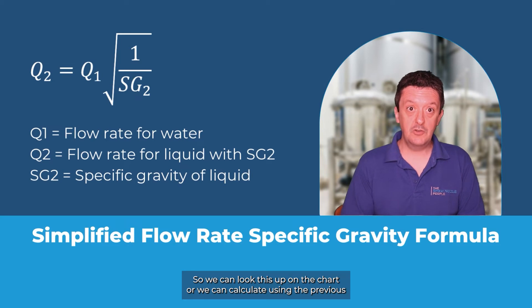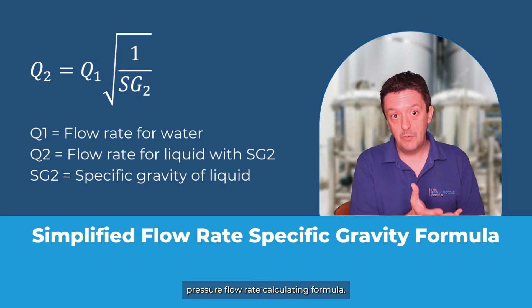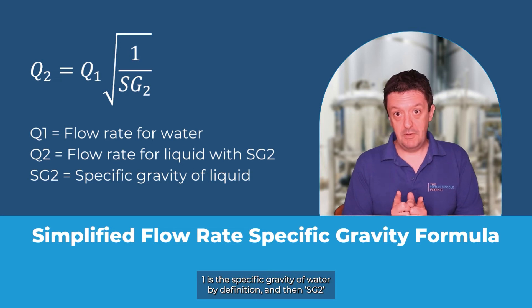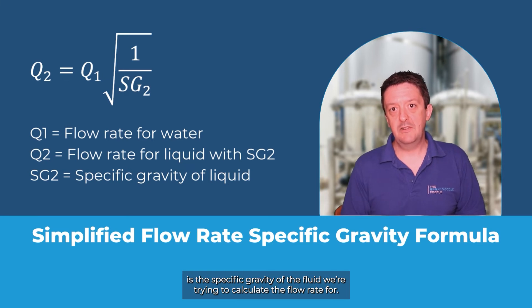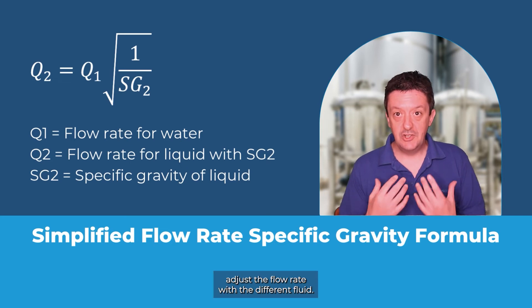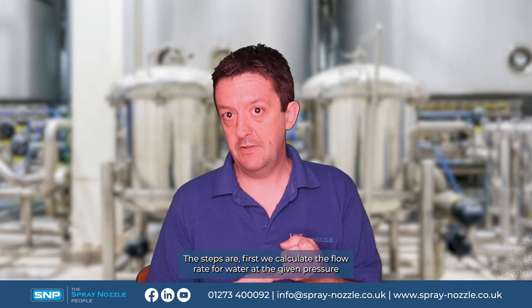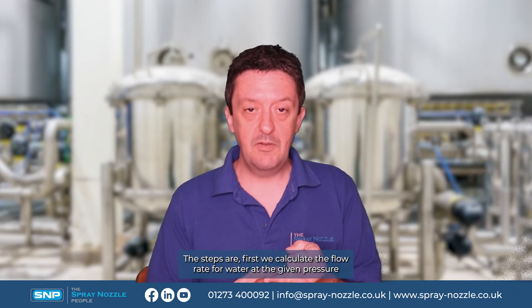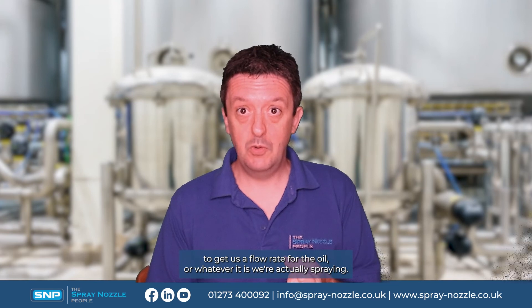So Q2 is the flow rate we're looking to calculate, and Q1 is the flow rate we know for water for this specific nozzle — which we can look up on the charts or calculate using the previous pressure flow rate formula. SG1 is the specific gravity of water, which by definition is 1, and SG2 is the specific gravity of the fluid we're trying to calculate the flow rate for. The steps are: first calculate the flow rate for water at the given pressure, then use this formula to adjust it to get the flow rate for the oil or whatever fluid we're actually spraying.